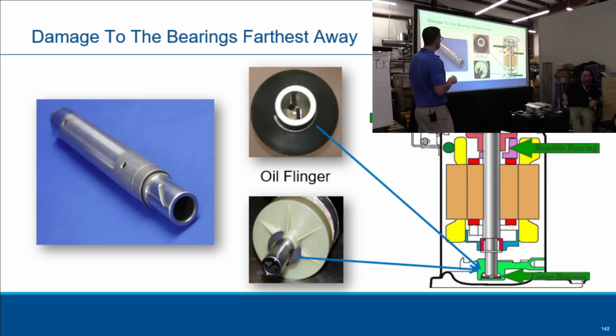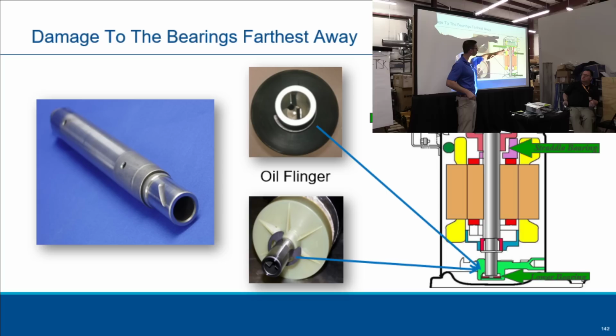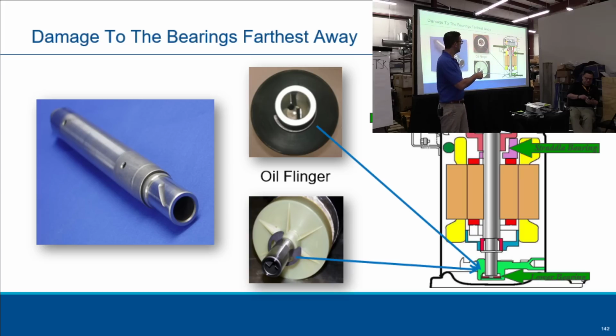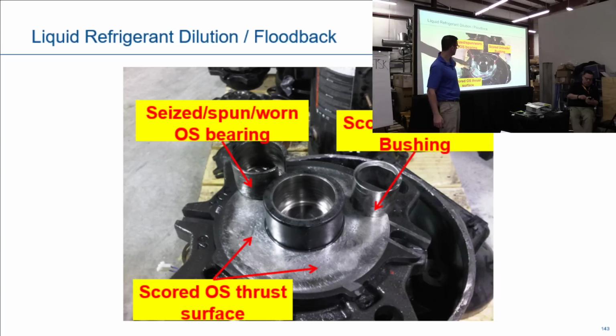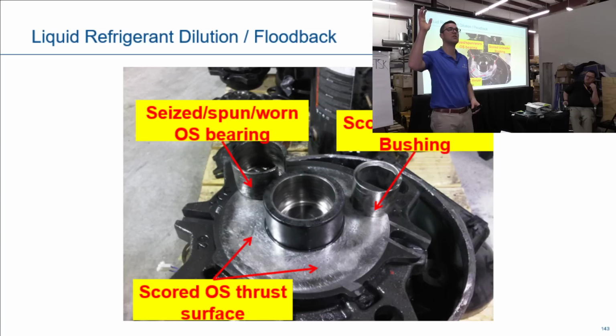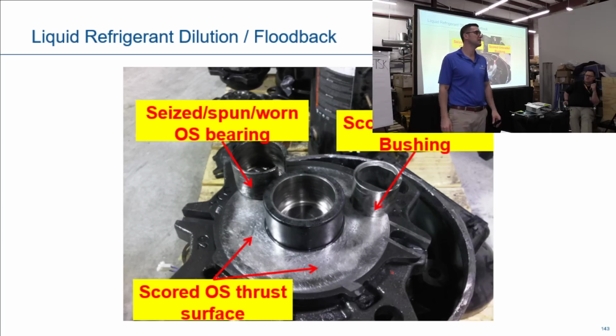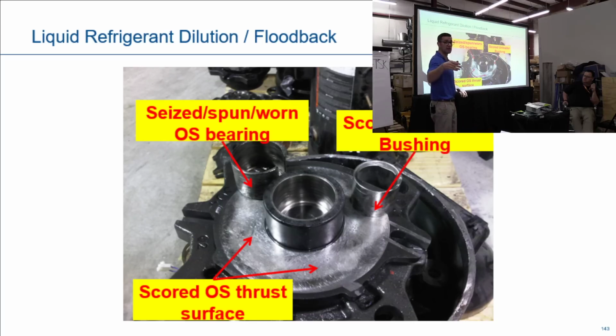The way it works here on a scroll, your suction comes in on the suction side, and your oil and refrigerant come back cooling the motor. But if you start getting liquid refrigerant coming back, it goes up the flingers and then wears out the drive bearing bushing. This is what it looks like. We call this scroll galling, and the bearing fails. If anybody hears a scroll go knock, knock, knock, that's not saying it is, you have to cut it open to find out, but that's probably something going on here, because it's going back and forth. Your amps will be a lot higher too.